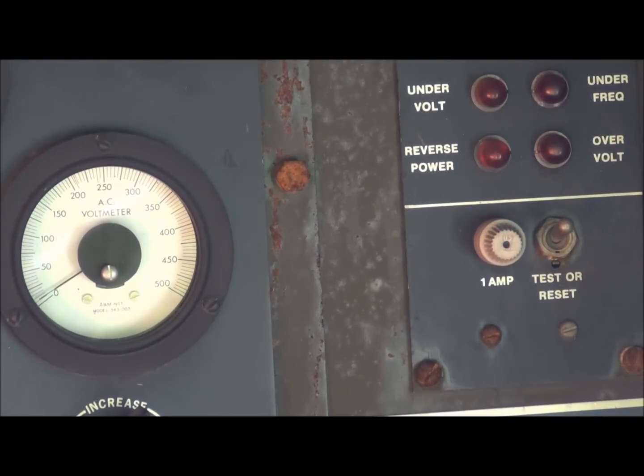Alright, I'm going to demonstrate the problem we're experiencing here with the over voltage on the startup. Now you can see the voltmeter on the left right here. We're set up for 208 volts, 3-phase right now. So during normal operation, that's what the voltmeter actually reads, but when we're starting it up and it's flashing the field, we're getting about 250 volts or so, and that's tripping the generator on over voltage. So you'll see when I start it up the voltmeter spike, and you'll see the over voltage light, and then you'll hear the engine shut back down.